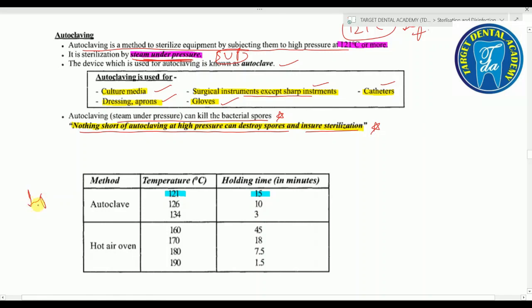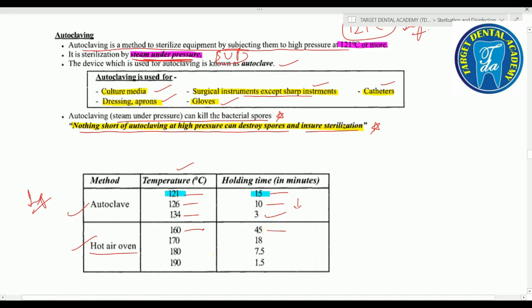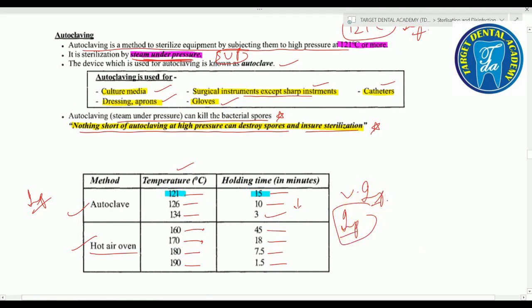Important distinguishing features between hot air oven and autoclave temperatures and times. Autoclave operates at three temperatures: 121°C for 15 minutes, 126°C for 10 minutes, and 134°C for 3 minutes — as temperature increases, time decreases. Hot air oven: 160°C for 45 minutes, 170°C for 18 minutes, 180°C for 7.5 minutes, and 190°C for 1.5 minutes. Very important.